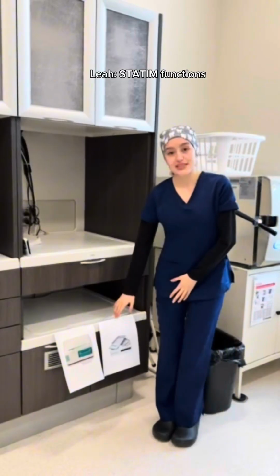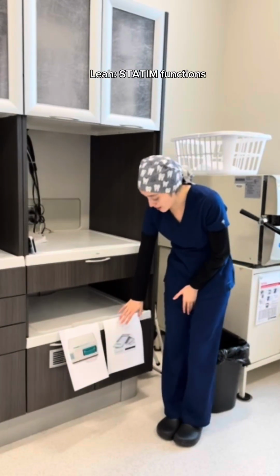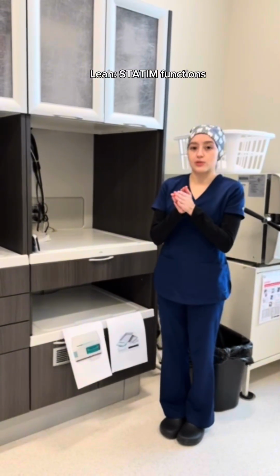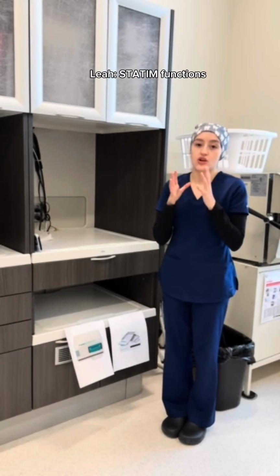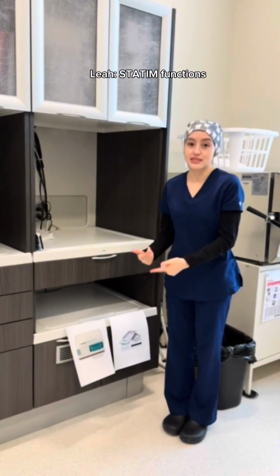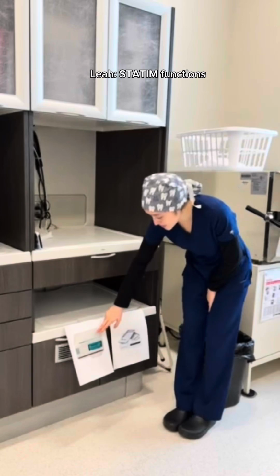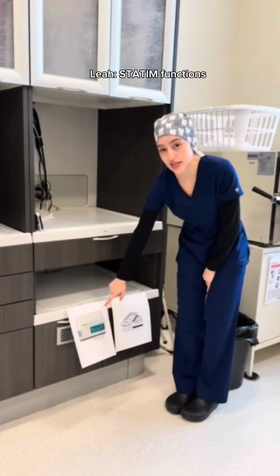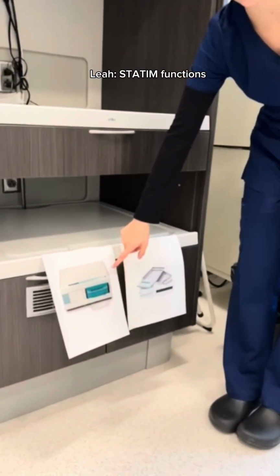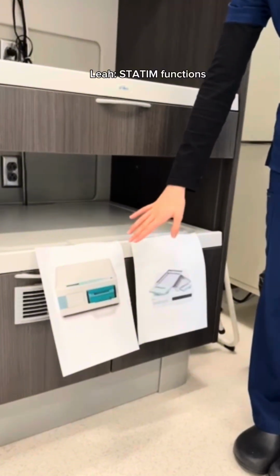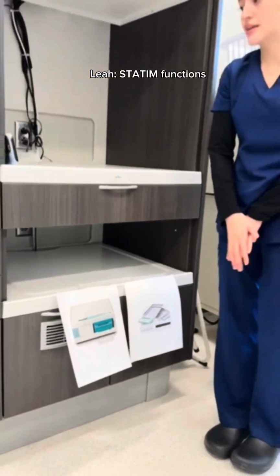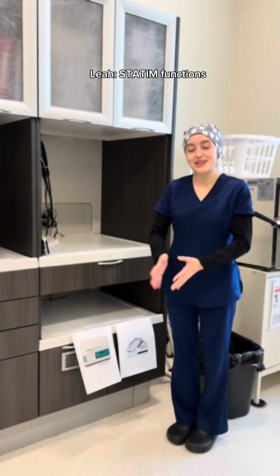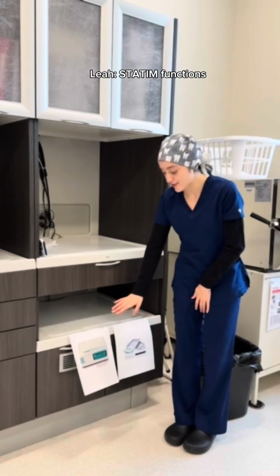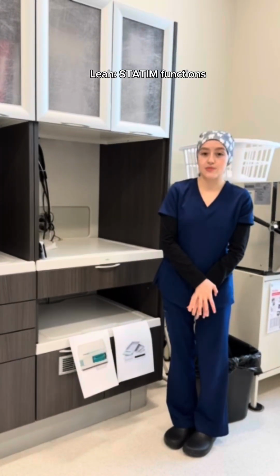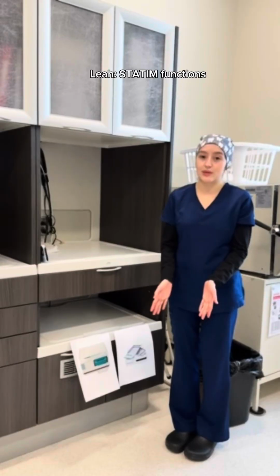Then we're going to load up the cassettes into the Statim. We got to make sure that they are separated properly so they're not all stacked together and they're not all squished so they can circulate and be sterilized properly. Then one of these buttons, I'm going to select the correct cycle for the type of instrument cassette that we have, if it's wrapped or unwrapped, and then press start. Sometimes there can be an error message. If that ever occurs, just look up the user manual to check the code and see what it means.